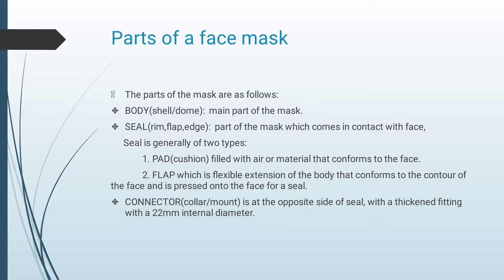Seal, called as rim, flap, or edge, is the part of the mask which comes in contact with the patient's face. Seal is generally of two types: pad or a cushion, which is filled with air or material which conforms to the face; and flap, which is a flexible extension of the body that conforms to the contour of the face and is pressed onto the face for a seal. Finally, connector or collar or mount is the opposite side of the seal with a thickened fitting with a 22mm internal diameter.